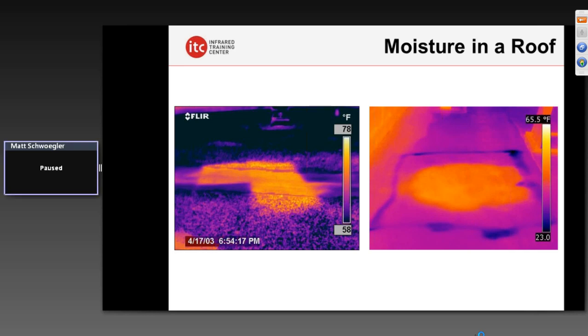Moisture is a big issue in buildings, certainly in low-slope roofs. Many commercial facilities have what's called a low-slope roof — a slight pitch. These roofs are susceptible to penetrations due to damage, improper installation, or sun exposure. Water can infiltrate beneath the membrane and be soaked up by the insulation. If not addressed, it's an energy efficiency issue because wet insulation conducts more heat. It's also a structural issue — that water can rust out the structural decking beneath and literally rot the roof apart. We want to identify this early on and can do so very successfully with infrared cameras.